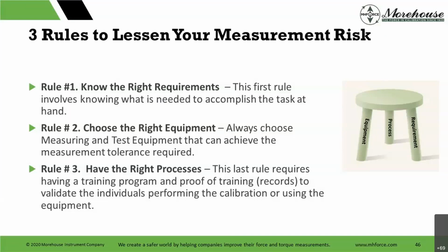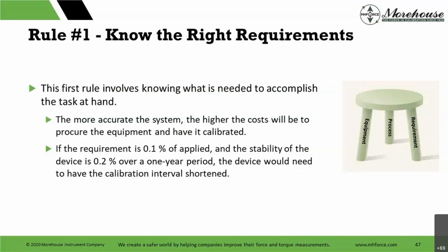So the three rules, basic: know the right requirements. The first rule involves knowing what is needed to accomplish the task at hand. Rule number two, choose the right equipment. Always choose measuring and test equipment that can achieve the measurement tolerance required. Have the right process. The last rule requires having a training program and proof of records to validate the individuals performing the calibration or using the equipment. So let's break it down.